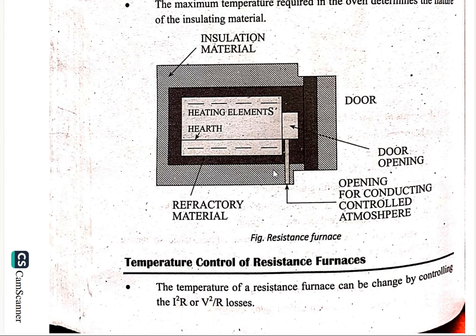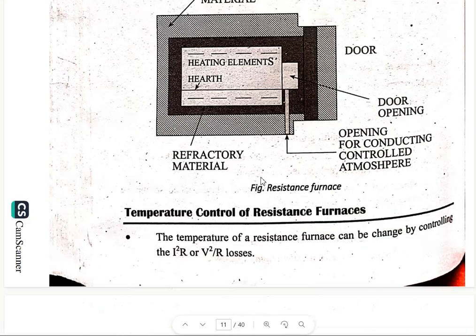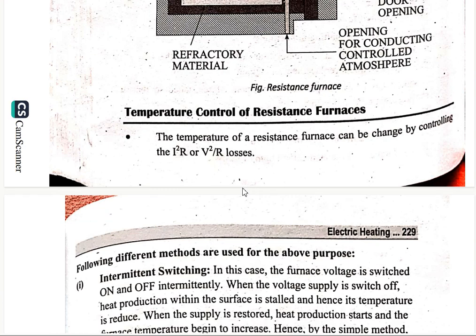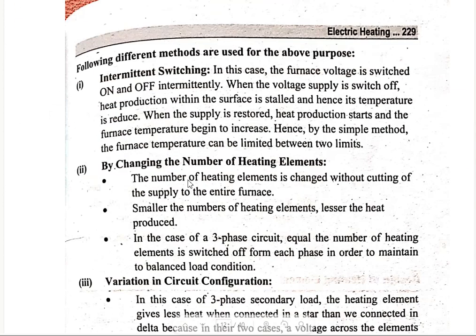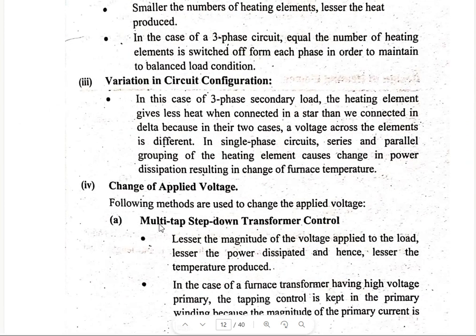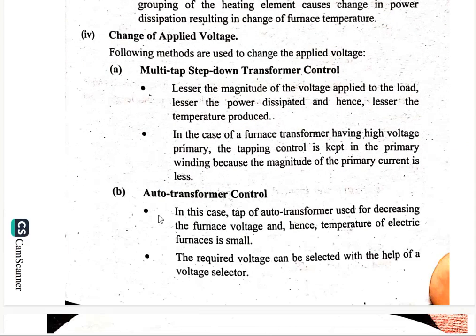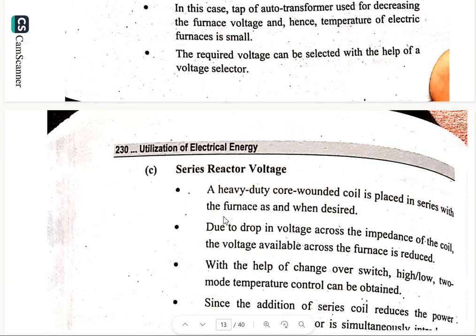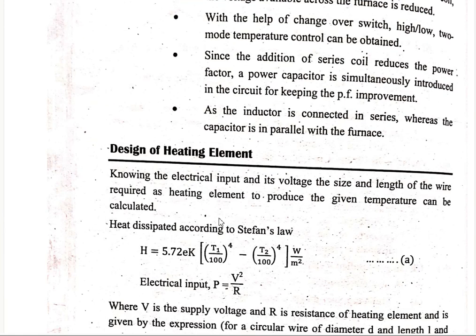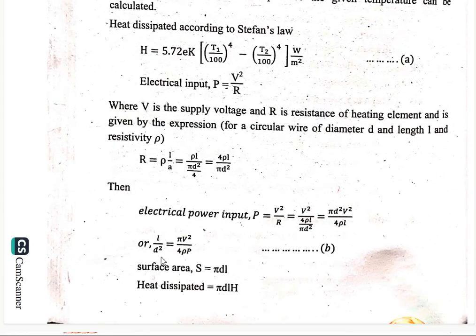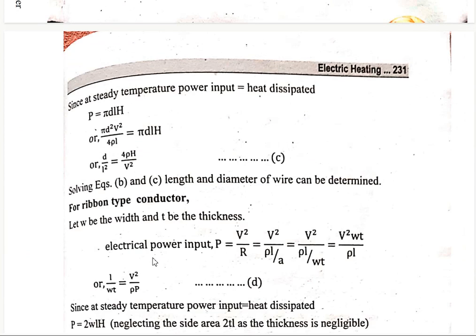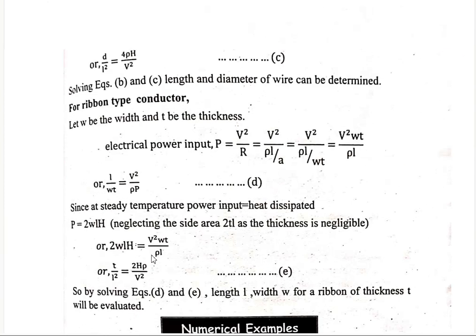For temperature control of resistance furnaces, different methods are used: intermittent switching, changing the number of heating elements, variation of circuit configuration, change of applied voltage, multi-tap step-down transformer control, auto-transformer control, series reactor voltage, and design of the heating element. The formula P equals V squared over R is important to remember for these calculations.